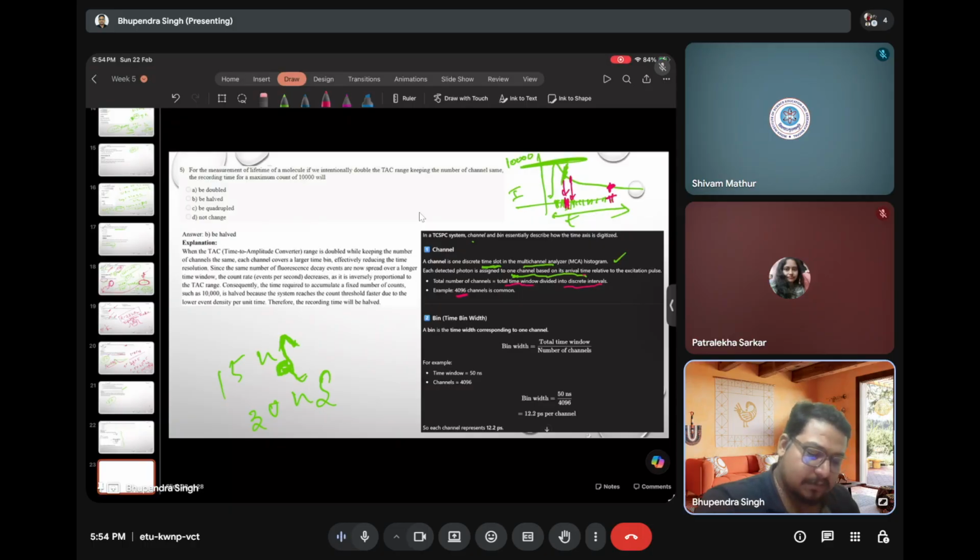So if the channel number is 4096, and initially, as I've already mentioned, the time window was 15 nanosecond, from this point to this point it is 15 nanosecond.